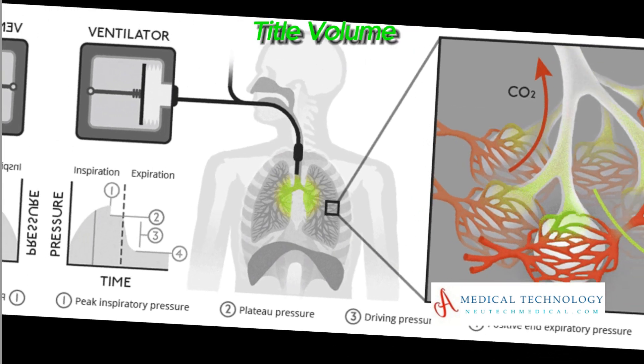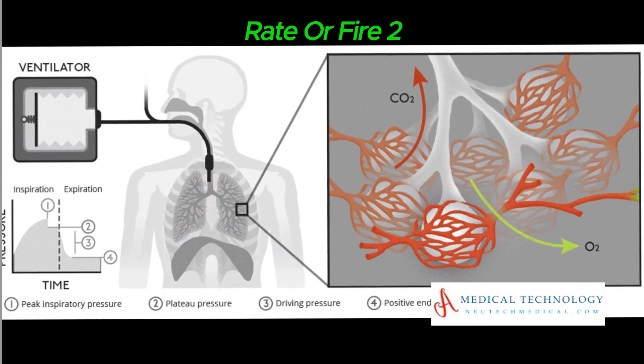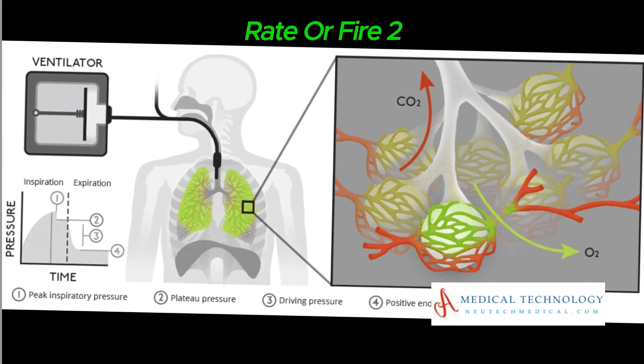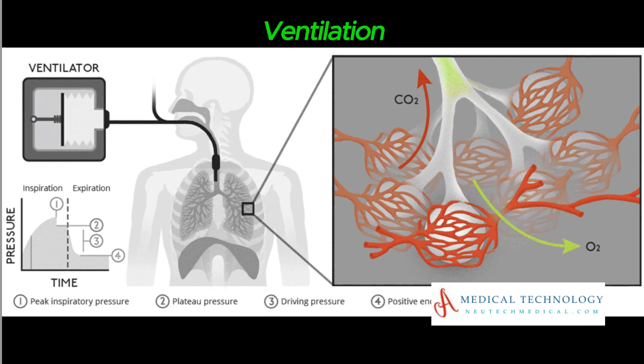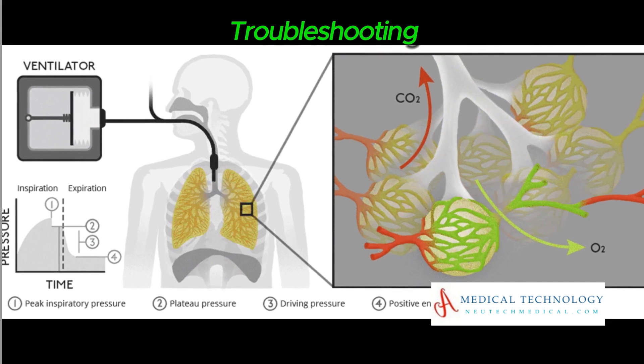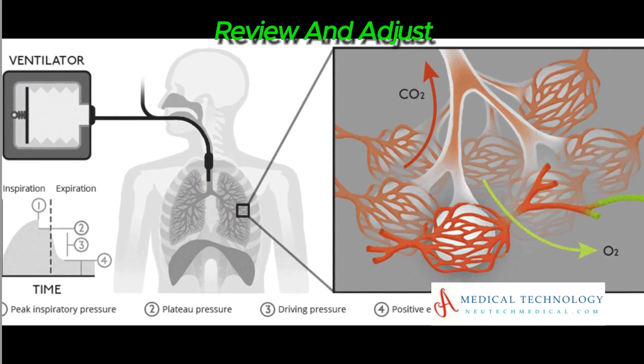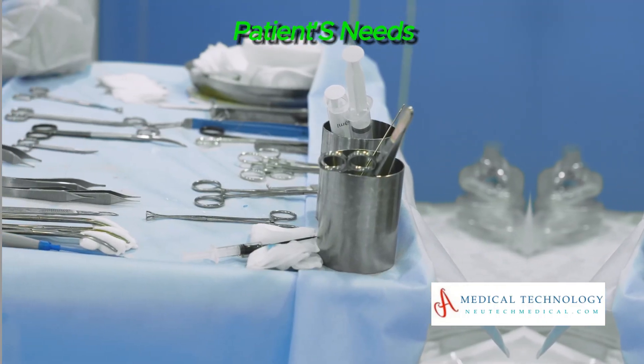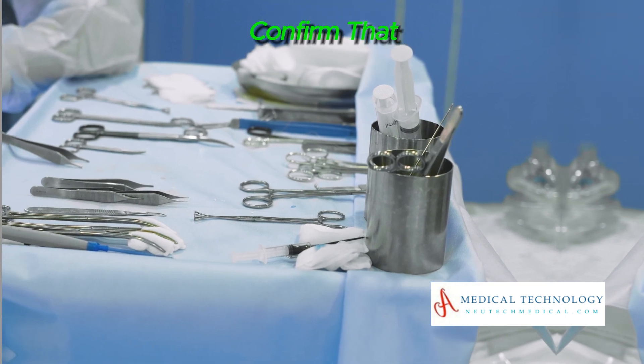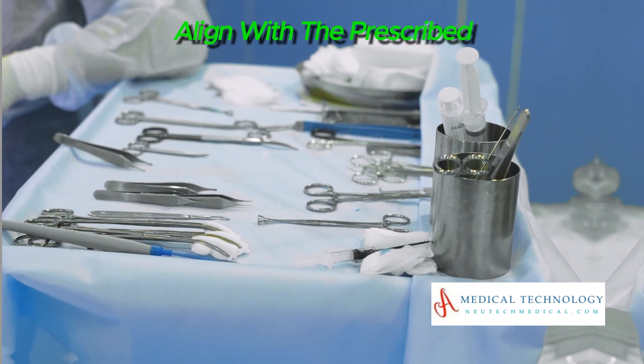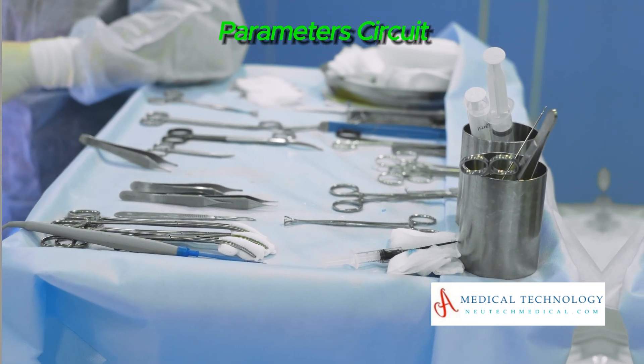Issue: Incorrect settings such as tidal volume, respiratory rate, or flow rate can compromise ventilation. Troubleshooting: Review and adjust ventilator settings based on the patient's needs. Confirm that the settings align with the prescribed parameters.